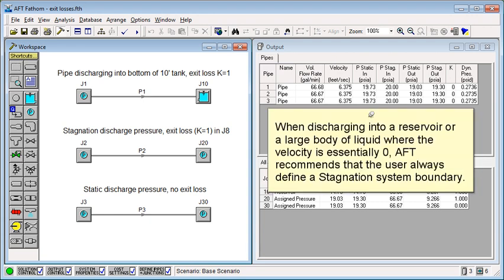When discharging into a reservoir or a large body of liquid where the velocity is essentially zero, AFT recommends that the user always define a stagnation system boundary.